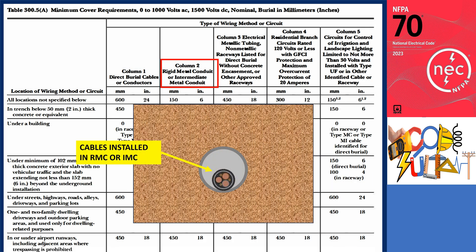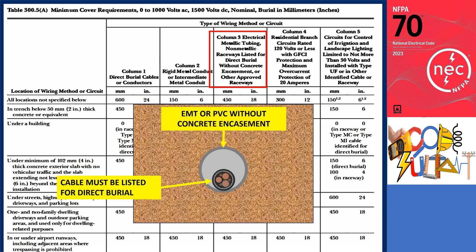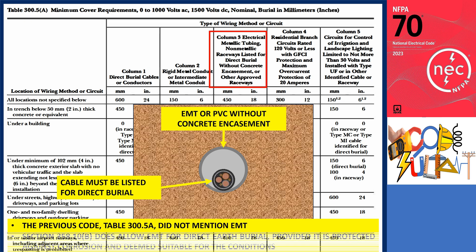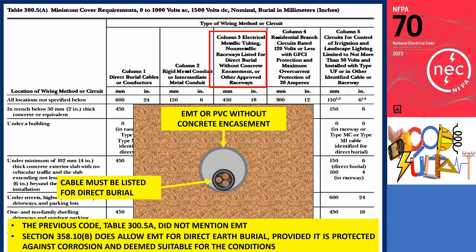Column 2 is for cables installed in rigid metal conduit or intermediate metal conduit. Column 3 pertains to conductors installed in electrical metallic tubing (EMT), non-metallic raceways listed for direct burial without concrete encasement, or other approved raceways. The previous Table 300.5(a) did not specifically mention EMT, leading some to believe EMT was not recognized for underground use. However, Section 358.10(B) does allow EMT for direct earth burial, provided it is protected against corrosion and deemed suitable for the conditions.